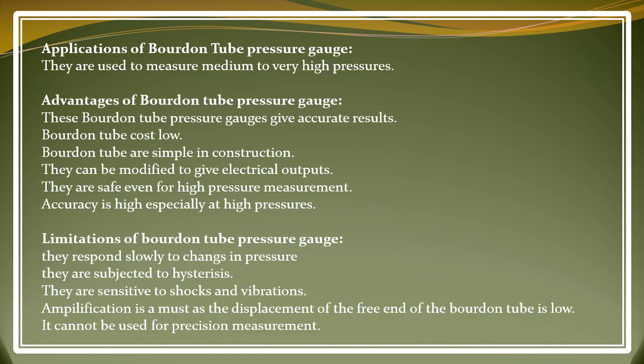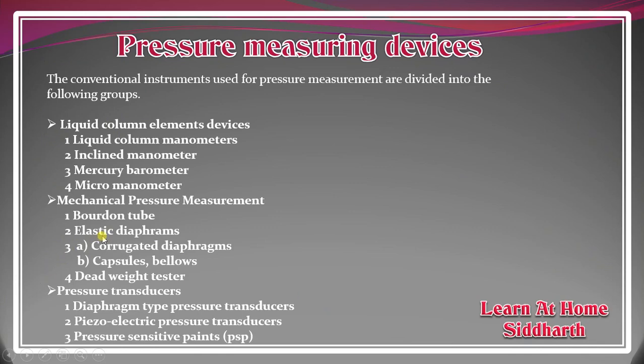Amplification is a must, as the displacement of the free end of the Bourdon tube is low. As you can understand, the Bourdon tube moves a very small quantity, so we have to amplify the movement of the Bourdon tube by the assembly of sector, pinion and all these things. So the Bourdon tube needs a mechanical system to amplify its motion. It cannot be used for precision measurement. As you can see, it lags in response, and it needs amplification, so it cannot be used in precision measurement. The second one is elastic diaphragms.